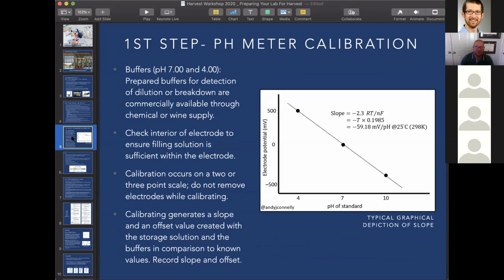So in terms of pH, we want to make sure that we're calibrating on a regular basis, and that we record the calibration. There are a couple of different values within the calibration step that are going to help you understand if you have an accurate pH reading. A lot of people just do a 2-point calibration, and that is sufficient. That is what pH has been based on for a long period of time. If you want to increase the accuracy of your pH measurement, you can use a 3-point calibration. It's very difficult to get a 10 buffer, and it is also more expensive. But it is helpful because most of the pHs that we see in wine are between 2.8 and 4.2.